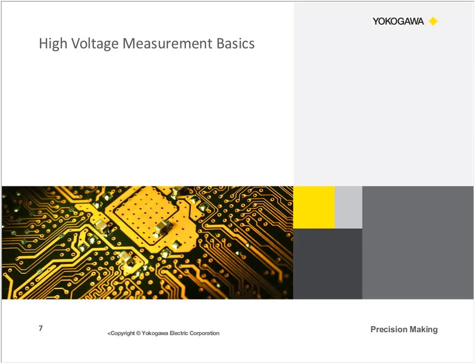So to get started, we first need to understand what is high voltage and what are the basic considerations that we should take when making these measurements. Now, the specific value for high voltage can change depending on the application that you're performing as well as the given standard. For example, IEC 60038 defines high voltage as any voltage greater than 1,000 volts RMS. Now, this is obviously going to be different, for example, from the ANSI C84.1 definition, which states that high voltage is anywhere between 69 kilovolts to 230 kilovolts.